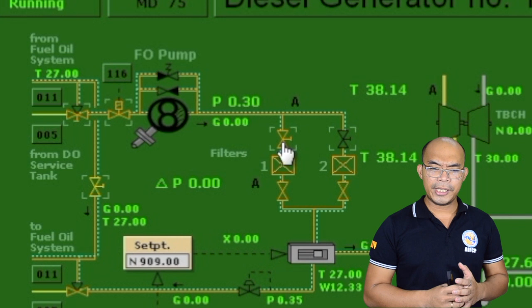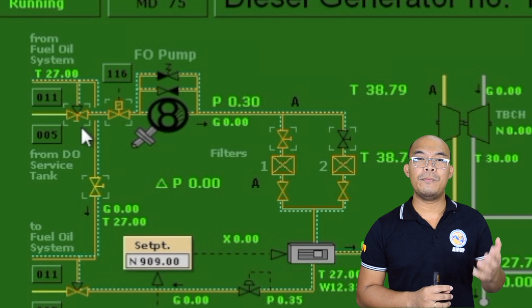Next is we have to check the position of the fuel oil supply three-way valve, make sure it's correctly set. It should be on diesel oil first, then later we change it over for our heavy fuel.